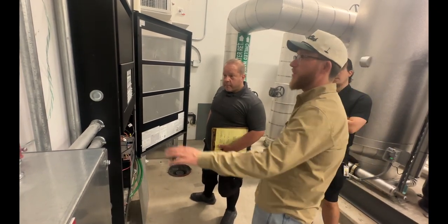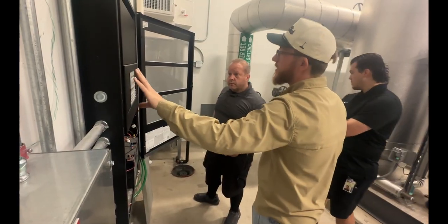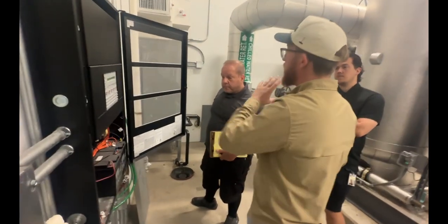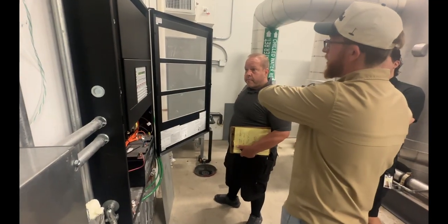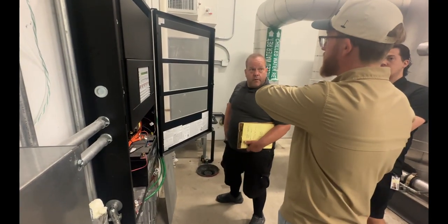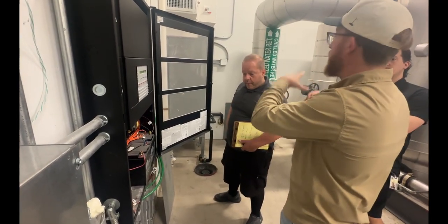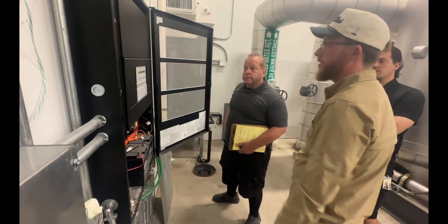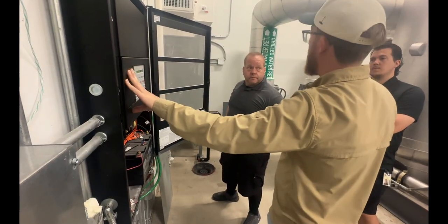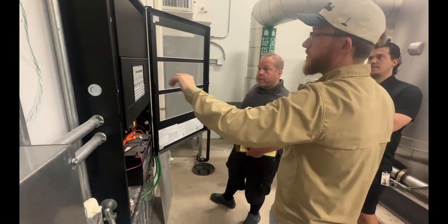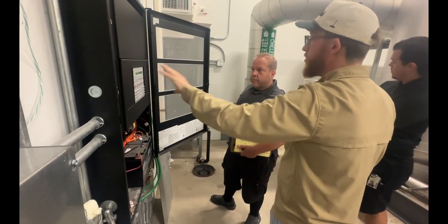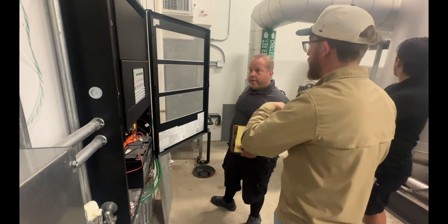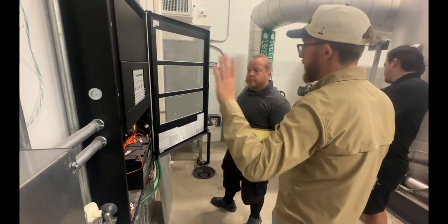So from this panel as well, you can't silence it from the annunciator, but you can acknowledge the trouble. The trouble, if there is one that comes in from here, will be broadcast to your office and the kitchen and all of those other channels, and you can acknowledge it there. But you'll definitely have to come back out here to silence this panel. You can also reset this in your office, not the other LCD ones.